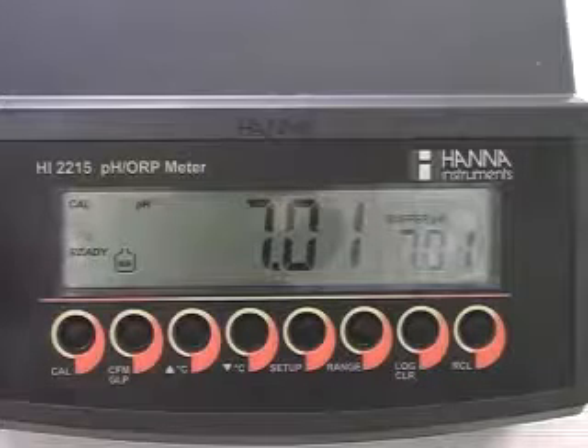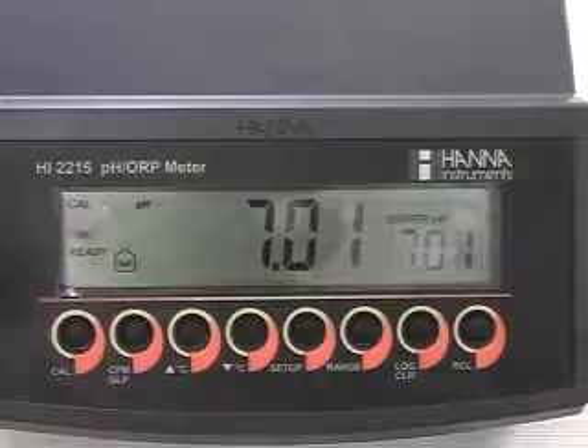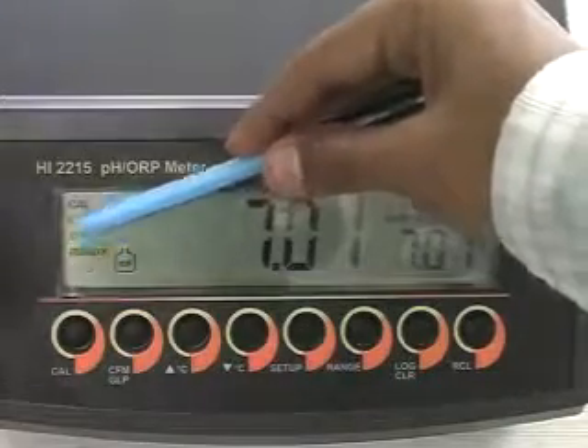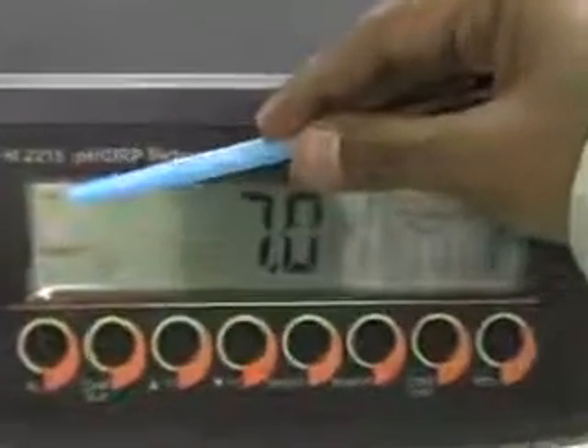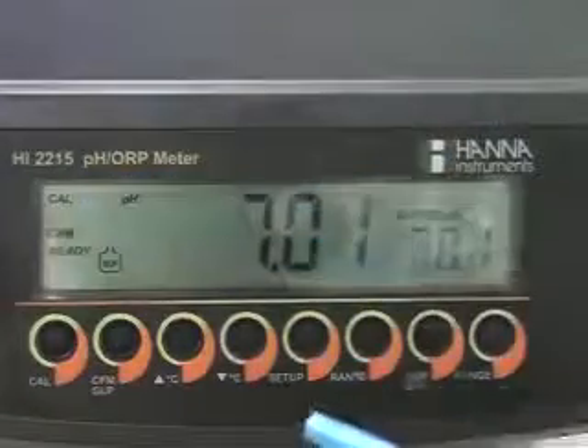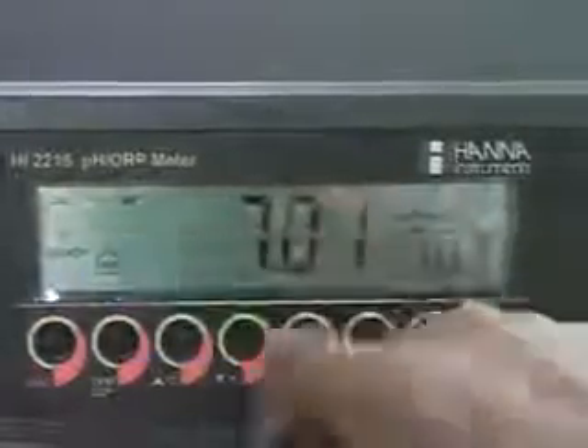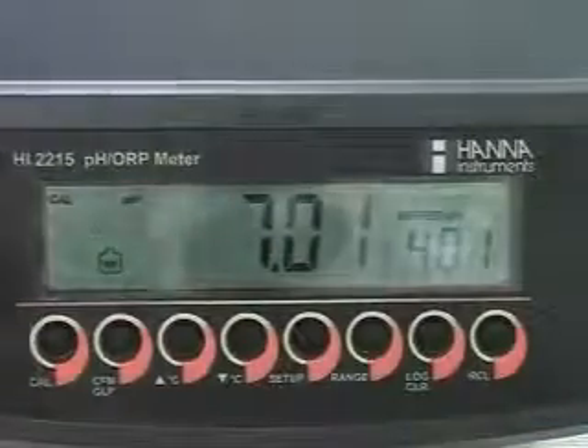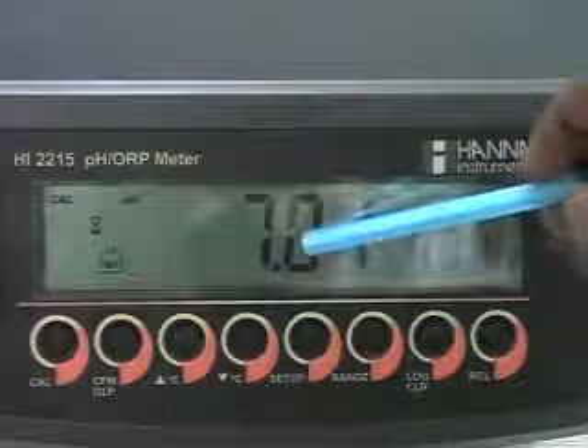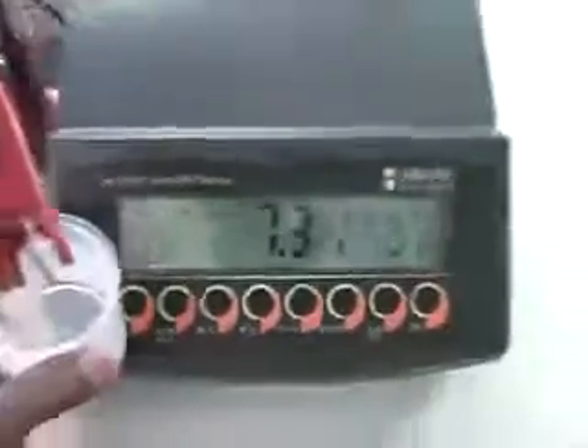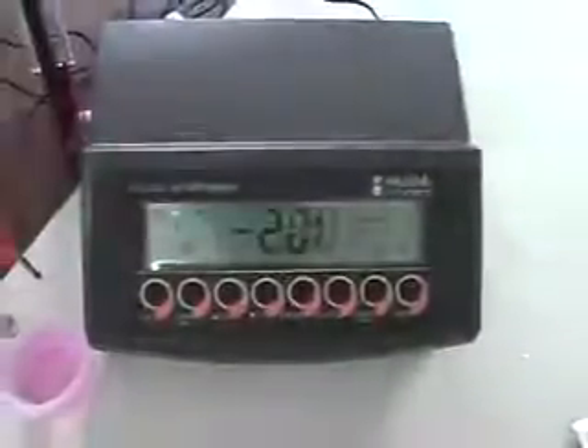When the reading is stable and close to 7.01 pH, the instrument will display ready and a blinking CFM tag. At this time, press the CFM key to confirm the calibration. After this, the instrument will show the calibrated value and the second buffer solution, 4.01 pH. Then clean the electrode with the distilled water and submerge your electrode into 4.01 buffer solution.